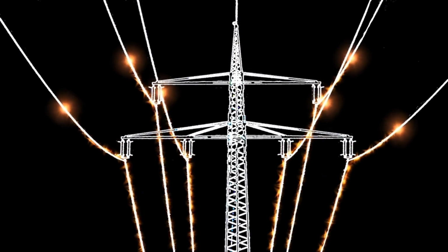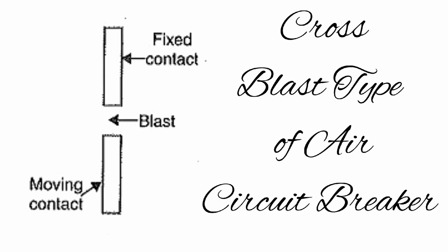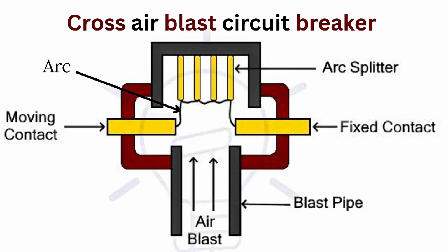Another type of air blast circuit breaker we will look at is the cross blast type. The cross-blast type of air blast circuit breaker, ABCB, is designed where the air blast is directed at right angles to the arc path. When an arc forms between the contacts of the circuit breaker, the compressed air is blown across the arc, effectively cooling and extinguishing it. This design is particularly useful in applications where the arc is longer and more unstable, as the cross-blast helps to rapidly cool the arc and increase its resistance, ultimately leading to arc extinction.